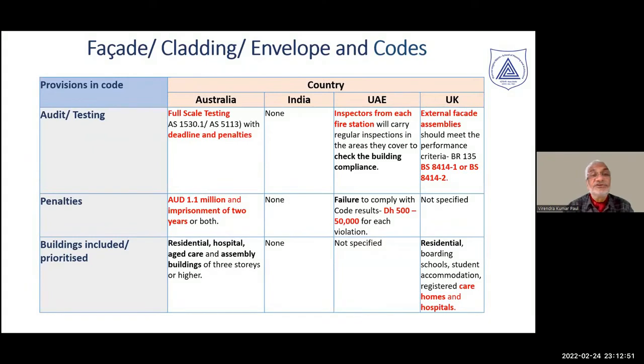On audit and testing, full-scale auditing is required. In Australia, AS 1530 and AS 5113 require full-scale testing, whereas in India only a smaller cluster sample is required — the two testing procedures and objectives are very different. In UAE, inspectors from each fire station are required to regularly carry out inspections and check compliance. In UK, external facades must comply with performance standards. There are stringent penalties in Australia and UAE; however, in India and UK, there are no such provisions.